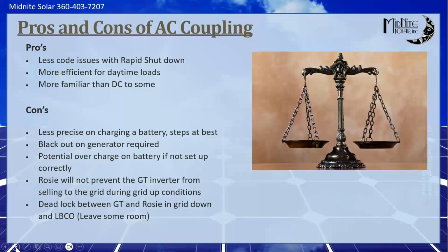Another con is, depending on your inverter, you may need a blackout relay for a generator. Like on the Rosie, for example, you will need a blackout relay. If you're using a Magnum, you'll need a blackout relay. If you're using our all-in-one, you can get away without the blackout relay as long as you use the generator input on the all-in-one and the AC coupling input for your AC coupled. They will lock each other out in software inside.